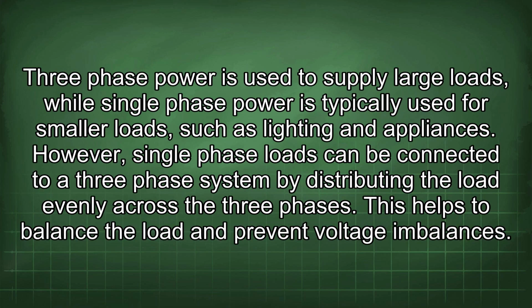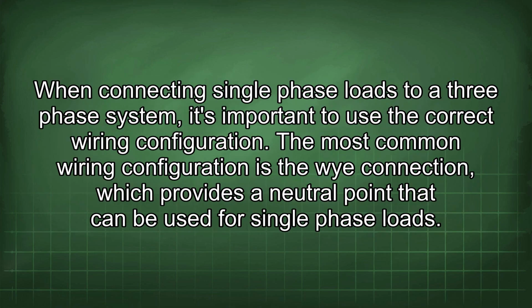Three-phase power is used to supply large loads, while single-phase power is typically used for smaller loads such as lighting and appliances. However, single-phase loads can be connected to a three-phase system by distributing the load evenly across the three phases. This helps to balance the load and prevent voltage imbalances. When connecting single-phase loads to a three-phase system, it's important to use the correct wiring configuration.